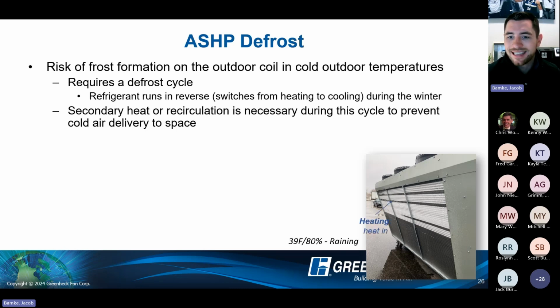That basically says, instead of grabbing heat out of the outdoor air, let's discharge it from the compressor, that hot gas, and reject it at this condenser coil now in cooling mode so that we can melt those frost conditions. And in those situations, you need secondary heat or some sort of recirculation so that you can prevent cold air delivering directly to the space.